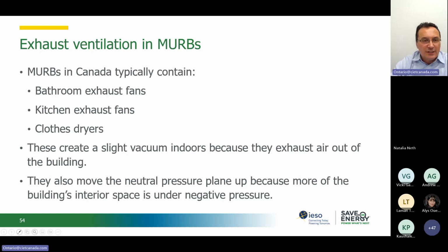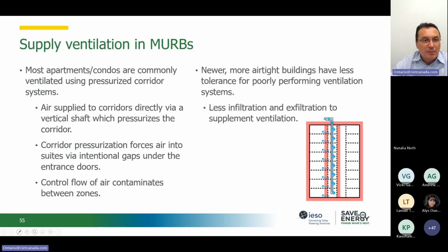So traditionally, or in a conventional type of design, we supply air to ventilate buildings in common areas. We do that through the corridors. We pressurize the corridors to prevent air coming from the units into the corridor. And then we also compensate for the air that is exhausted. So this, in a design environment, will look perfectly fine. And sometimes in operation, we see problems there because it's not balanced, and still air coming from the units will be pulled into a slightly negative environment in the corridor caused by, let's say, the stack effect.